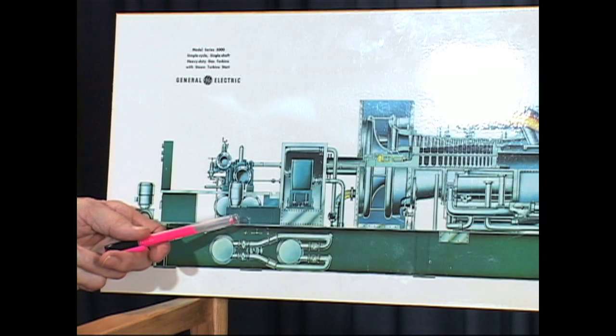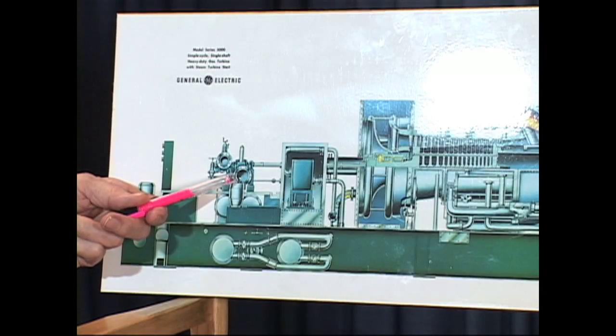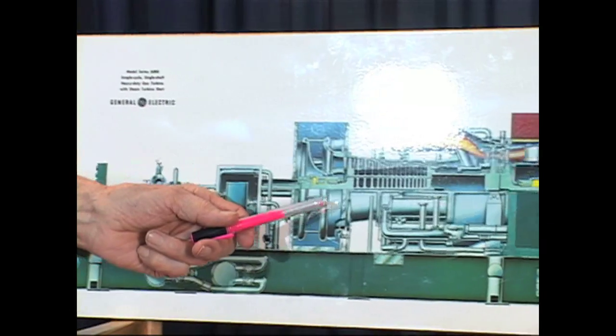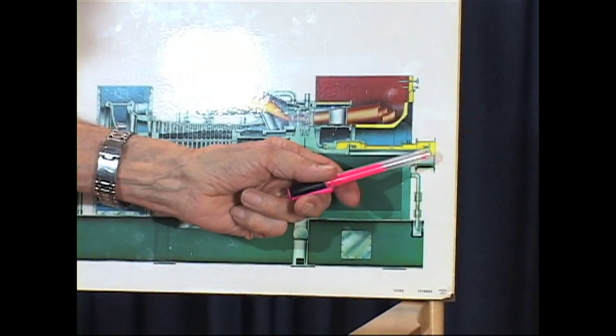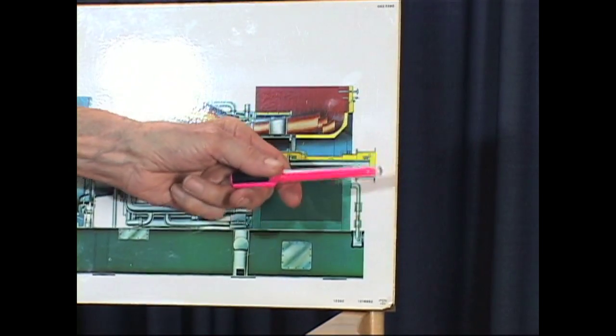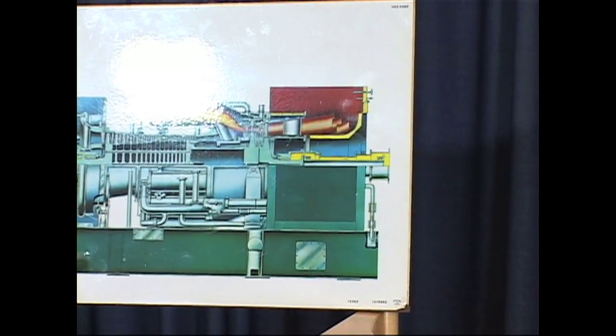Once you're up to speed and get the generator, if that's what it is, synchronized, get it online, then you put more and more fuel. Now you cannot change the speed anymore, but you can put more and more fuel in and the torque increases. And the generator over here would generate more and more kilowatts.